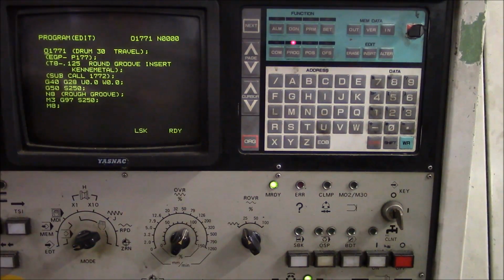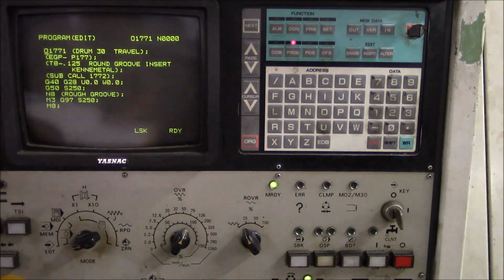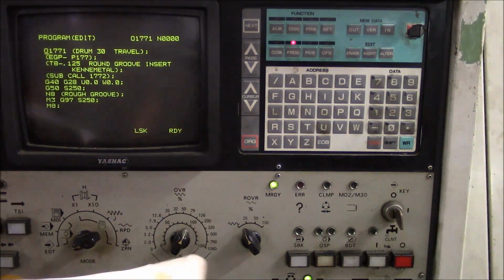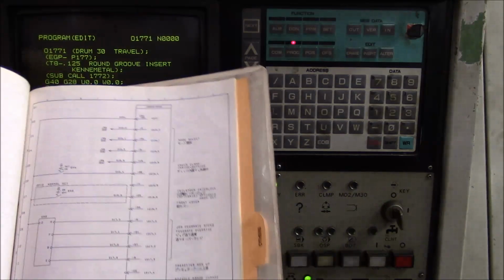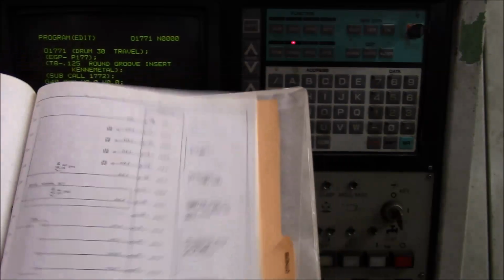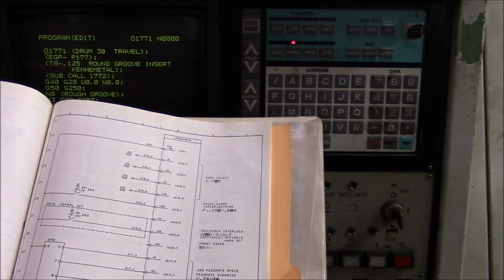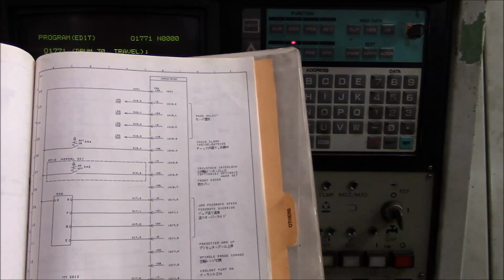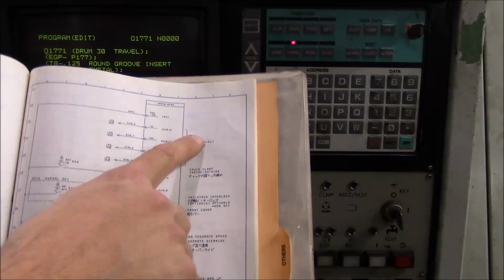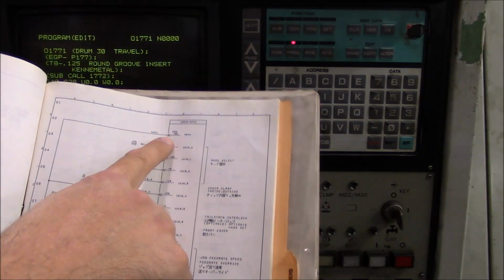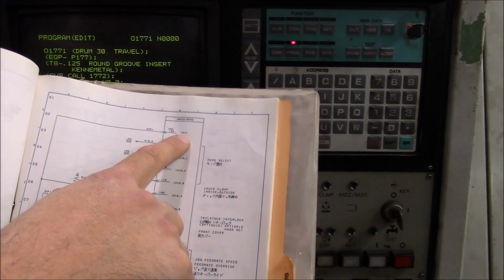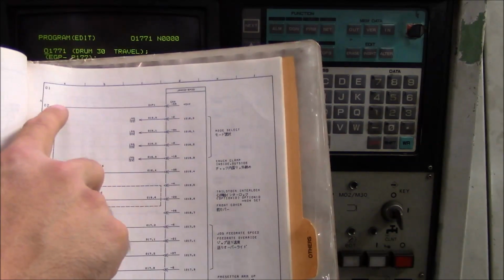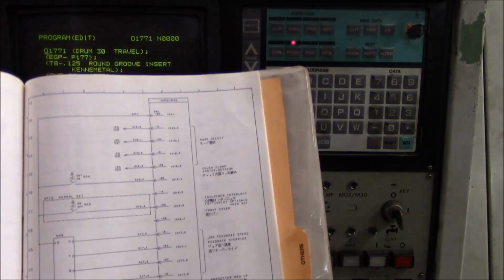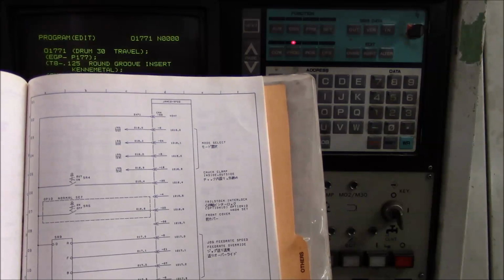I wanted to show you how to use the wiring schematic with the I/O functions of the control for troubleshooting. If we look at a page in the schematic like this, we see some descriptions along the side, like coolant pump off, coolant pump on, mode select, yada yada. Right here, this top rung is positive 24 volts, going out here, then through some various switches and back into the control.